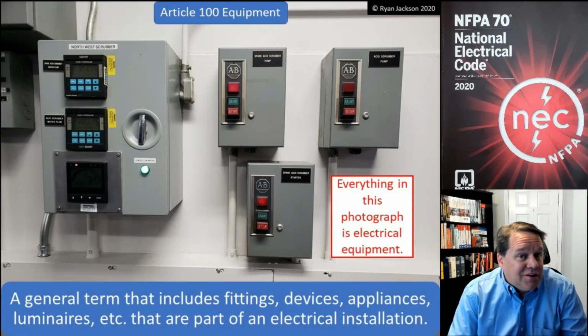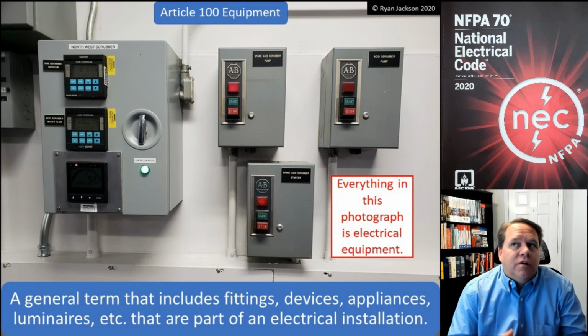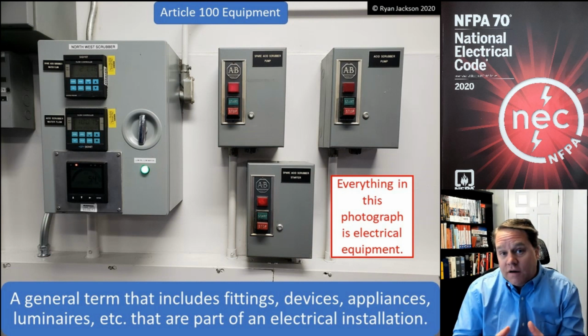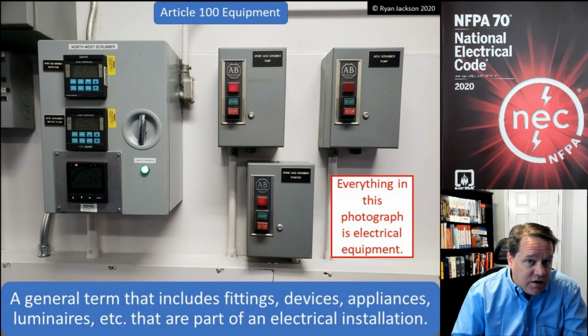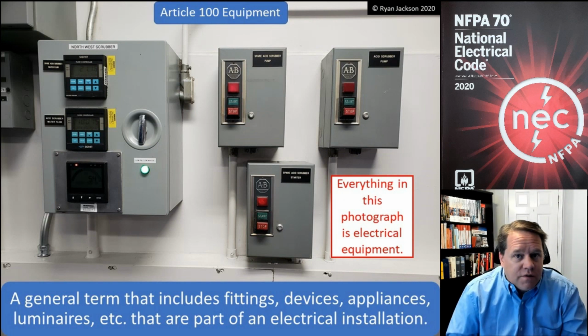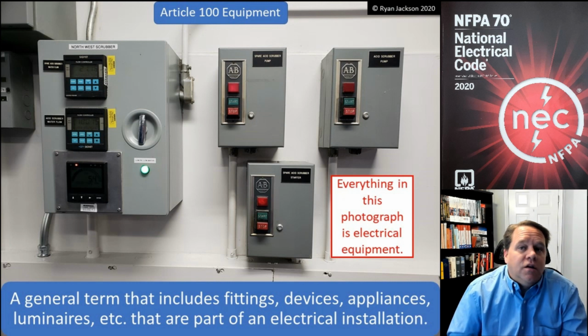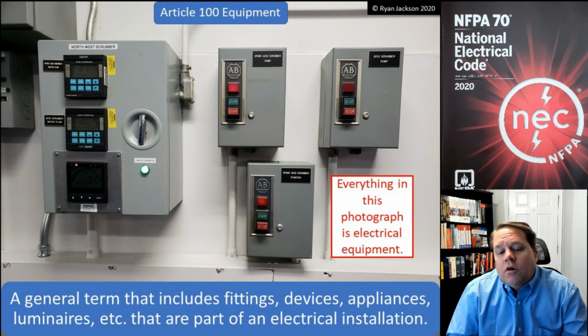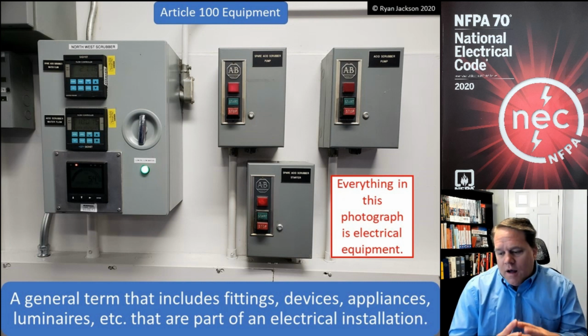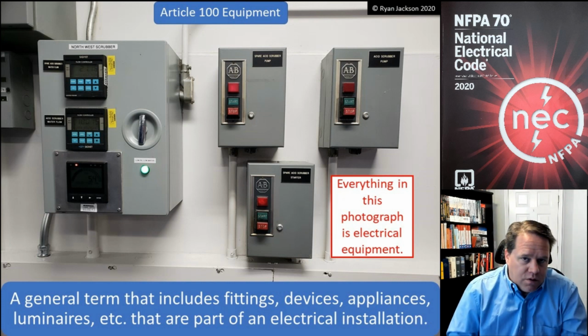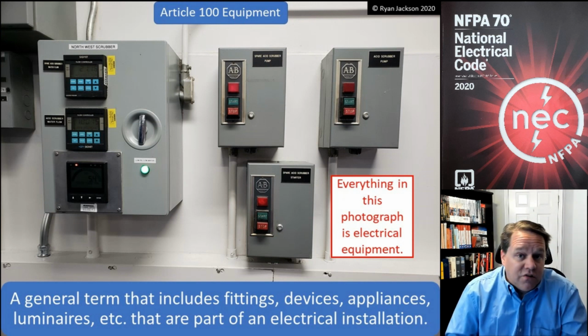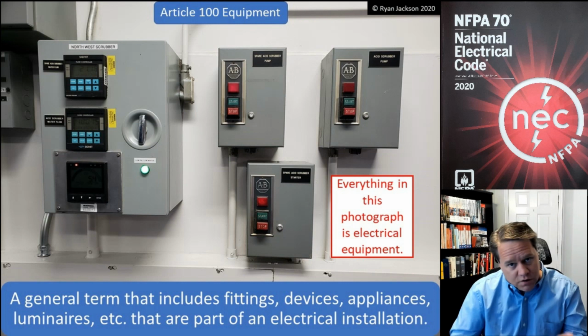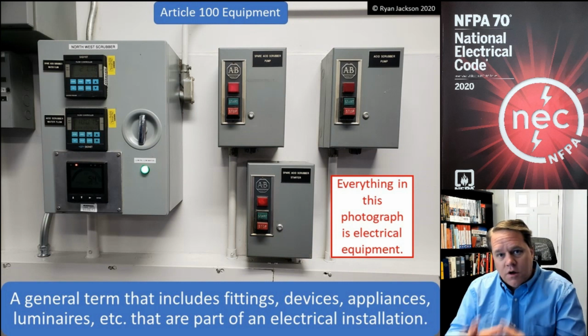You know, the definition of equipment in Article 100 is probably the most broad definition that we have in the NEC. It's a general term that includes fittings, devices, appliances, luminaires, and similar that are part of an electrical installation. Okay, everything you install is equipment. The only exception to that is conductors. So we install conductors and equipment.